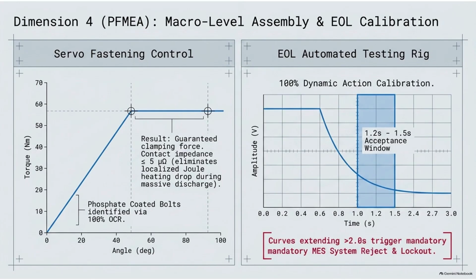I can't even fathom the amount of data storage that requires. Why do they need that level of granular data for a simple bolt? To guarantee contact resistance, they need the physical connection between those two thick metal plates to have an electrical resistance of less than 5 microohms. Microohms. Almost perfectly conductive. What happens if it's slightly looser than that?